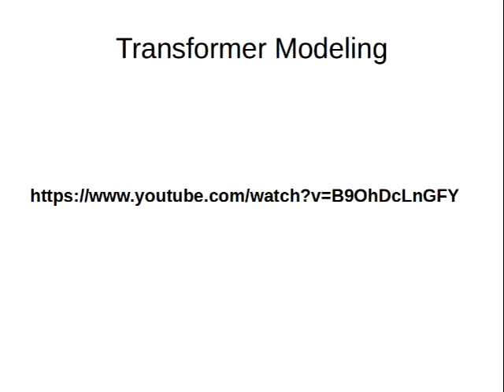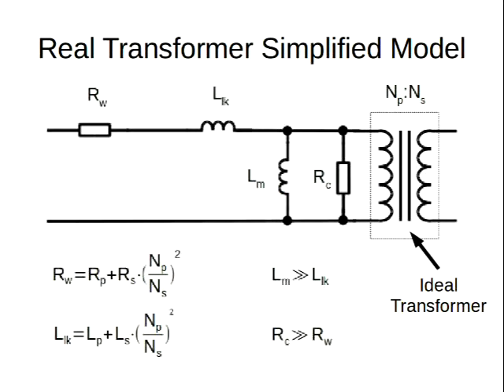But before we perform some measurements, let us review the simple model we established for a power transformer in the first video of this series. Power transformer simple circuit model. R sub W is the resistance of the secondary wire reflected on the primary plus the primary wire resistance. L sub Lk is the leakage inductance of the secondary reflected on the primary plus the leakage inductance of the primary. R sub C represents the core losses and L sub M the inescapable magnetizing field.